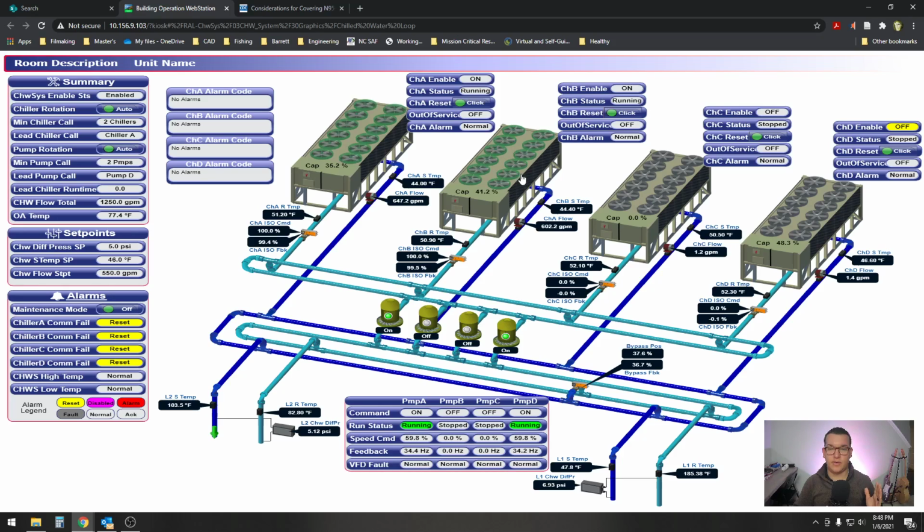And that's all that these chillers care about, is maintaining that supply water temperature. That's it. And that's all the chillers are looking at, is to maintain this. And as long as it has minimum flow and all the compressors are working well, this unit is going to give off that temperature.